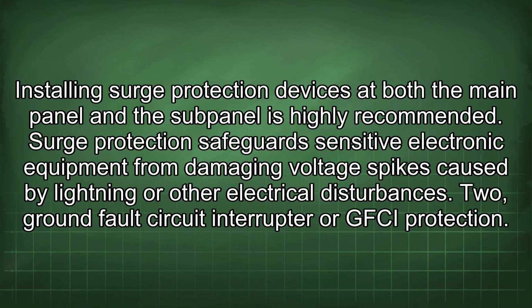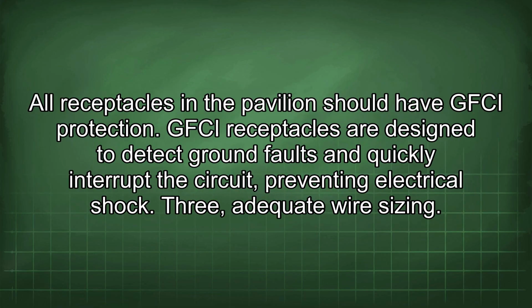Installing surge protection devices at both the main panel and the subpanel is highly recommended. Surge protection safeguards sensitive electronic equipment from damaging voltage spikes caused by lightning or other electrical disturbances. 2. Ground fault circuit interrupter, or GFCI, protection. All receptacles in the pavilion should have GFCI protection. GFCI receptacles are designed to detect ground faults and quickly interrupt the circuit, preventing electrical shock.